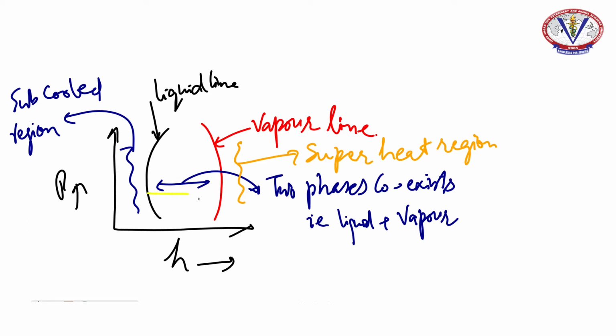On the pH diagram, the evaporation process is marked as a horizontal line parallel to the enthalpy axis, and this line lies between the liquid line and the vapor line. In case of superheating of vapors, this line may extend towards the area of superheat, and this line on the diagram is shown from point 5 to 1. From 1 to 2 the line shows the compression process, and it clearly shows that the pressure of the refrigerant vapors is being raised to a higher level, up to point 2.